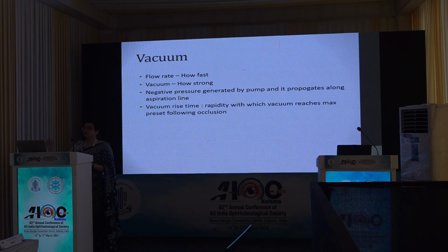The negative pressure which the pump generates propagates along the aspiration line, and with that the phaco probe holds the nuclear fragment. And vacuum rise time is the rapidity with which the vacuum reaches the maximum following the occlusion. So on that depends our emulsification power.